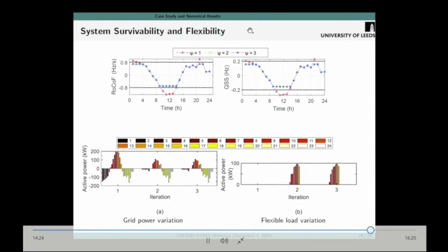In this second result, we looked at the survivability of the system with the dynamic islanding constraints. So the system grid code limits are represented by the thick dashed lines in both diagrams. And we notice for iteration 1, where we don't consider the dynamic metrics, we see a violation in both the rate of change of frequency limits, here considered in red, as well as the quasi-steady state limits. However, with every iteration, at iteration 3, represented by the blue markers, we see that the system operation remains within the grid code limits, which ensures that the system provides a transiently secure operation.